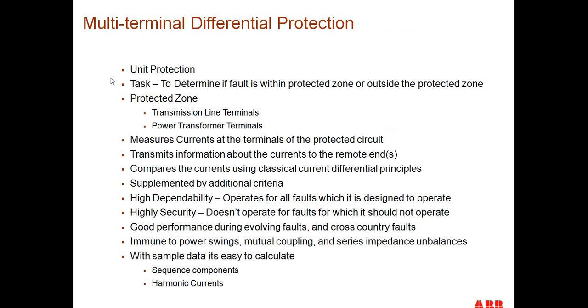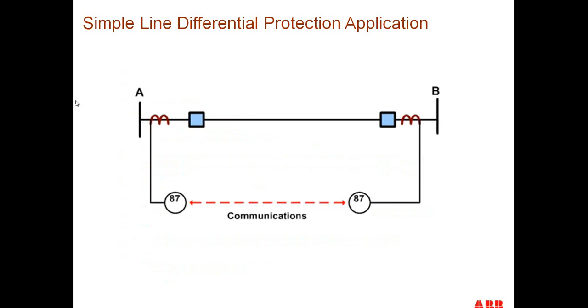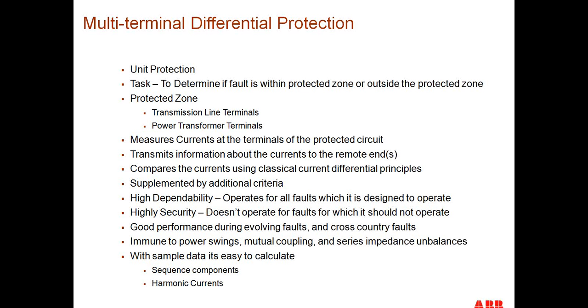So some things we can take away from this is the line current differential relay is unit protection. That means the protection is only concerned with what's between the two current transformers, what's between the two sets of CTs. Anything external to the CTs is not in any protection zone. So we have a definite area of protection that we're limiting our protection to. The test simply is then to determine if the fault is within the protected zone or outside the protected zone.